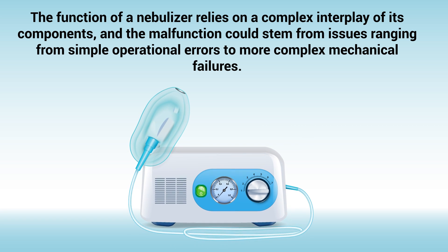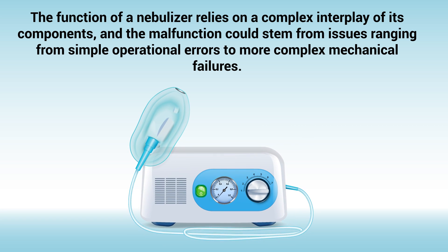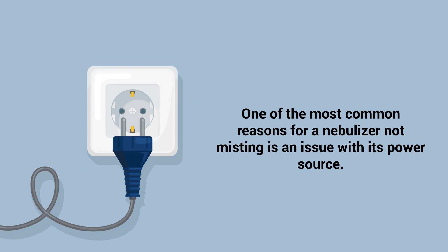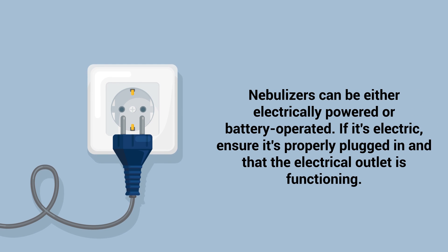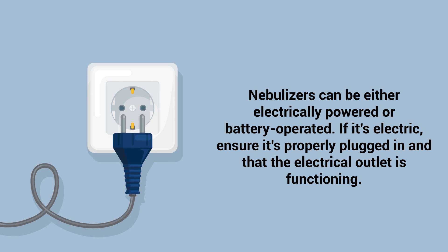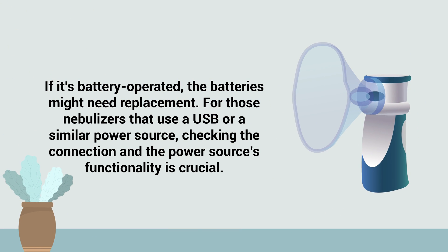A malfunction could stem from issues ranging from simple operational errors to more complex mechanical failures. One of the most common reasons for a nebulizer not misting is an issue with its power source. Nebulizers can be either electrically powered or battery operated. If it's electric, ensure it's properly plugged in and that the electrical outlet is functioning. If it's battery operated, the batteries might need replacement.